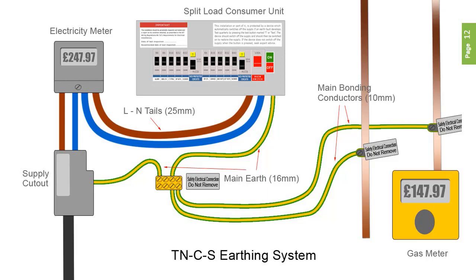Almost all new supplies for dwellings will be from a PME distribution system. It's easy to spot, as the earth is provided from the distributor's fuse cutout and can be seen coming out of the side, where it is connected to the incoming PEN or Protective Earth Neutral Conductor. The maximum earth fault loop impedance for a TN-CS system is 0.35 ohms.